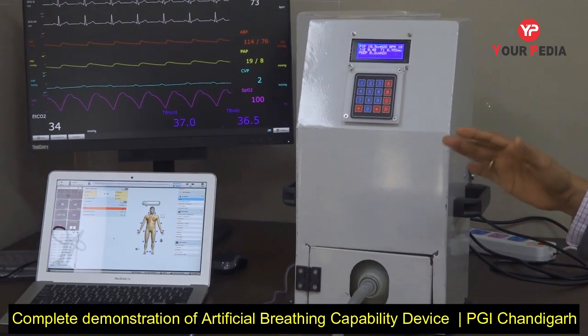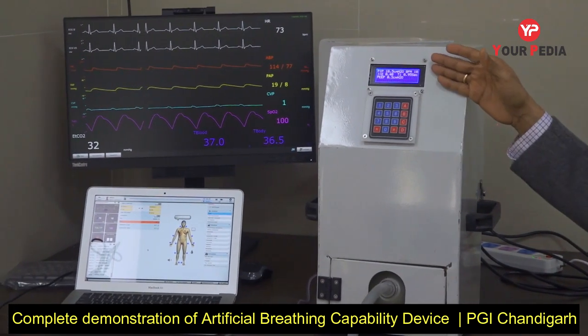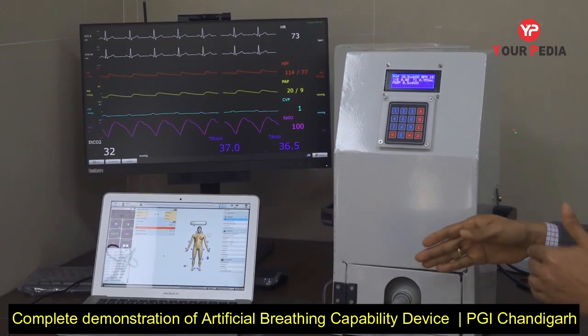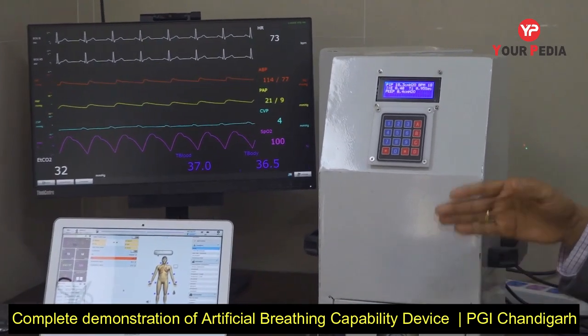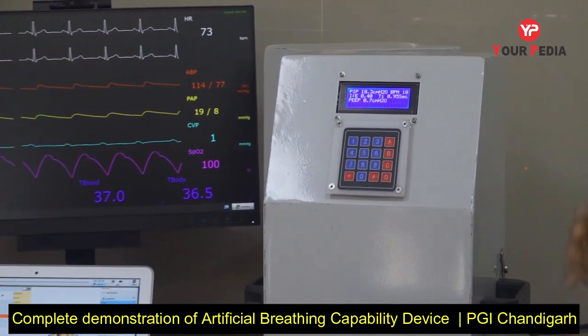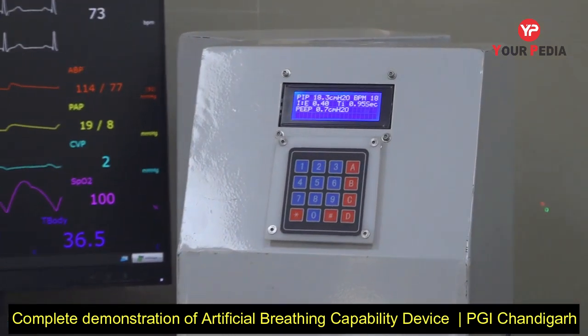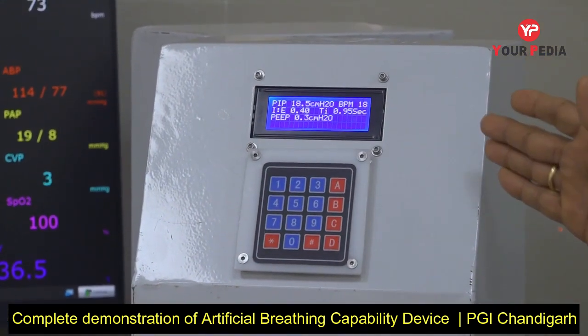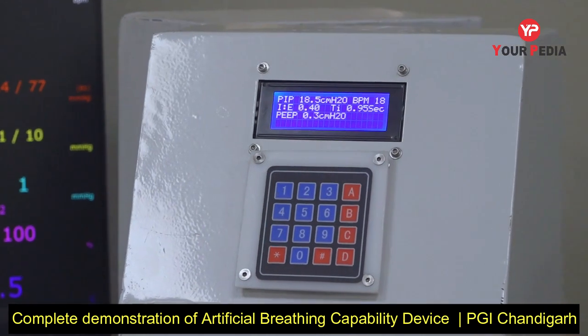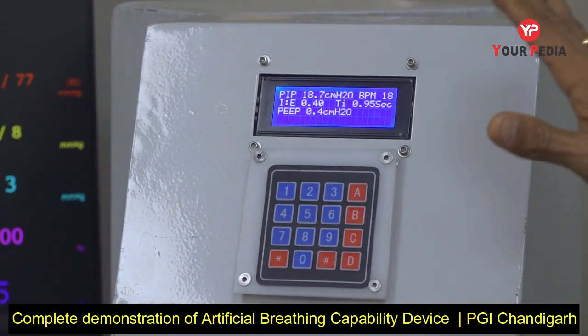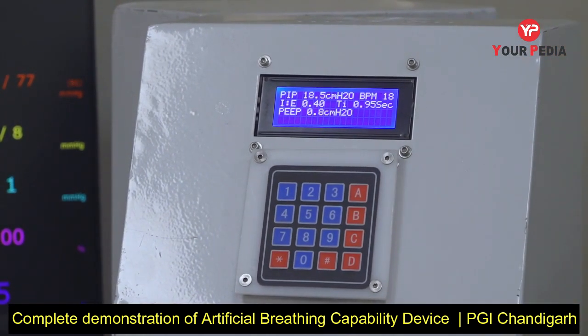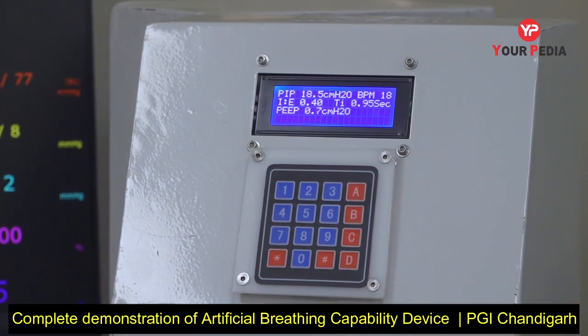This also has other additional features. You will observe on the screen that as soon as the ventilator tubing was disconnected, without any lag, the preset pressure has been recorded and it is actually delivering. The screen on the machine actually displays what is happening with each breath. So these are not the set parameters, these are the parameters which are being delivered with each breath and read on the display screen over here.